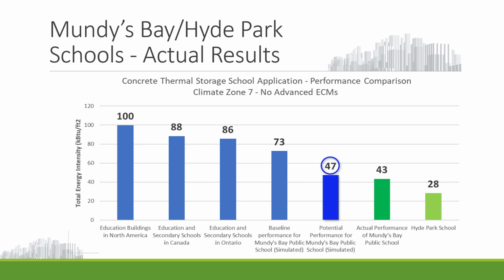You can see this 47 kBTU per square foot figure is much lower than the standard building in the modeling. The actual results turned out to be 43 kBTUs per square foot. The difference between the model and actual performance is that models don't pick up the gain attained from absorbing heat from occupants and equipment in the building. So the actual performance was better than what the model predicted.